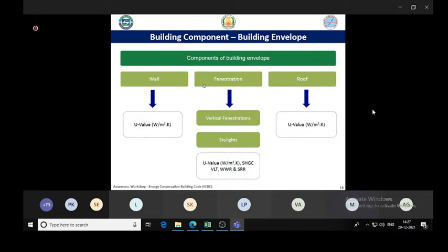In the envelope, there are 3 factors. It basically deals with the roof, the wall, and then the fenestration or glazing. For the roof and wall, the major requirements are the U value, the thermal conductivity of the wall and roof. Specifications are given. We will get into detail a little later. For the roof, we also have cool roof requirements. Whereas in fenestration, we have window to wall ratio requirements. We have the U value of the fenestration, SHGC, that is solar heat gain coefficient, and VLT. So we have these 4 requirements when we talk about fenestration.